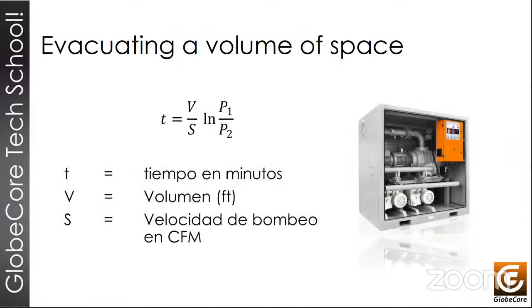Another widely used process is creation of vacuum, or evacuating a transformer. When we commission a transformer, this process is often used. A vacuum pump evacuates the transformer for a certain time, and then we measure the dew point to determine if the transformer is dry enough. Here you have a simple formula that tells us how long it will take for a vacuum machine to evacuate a transformer tank, or actually any closed space, a chamber.